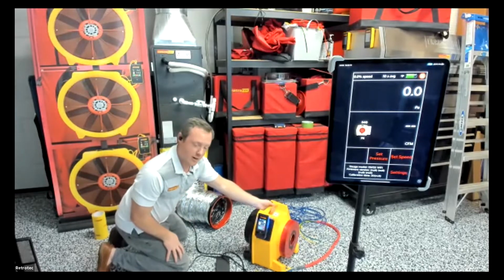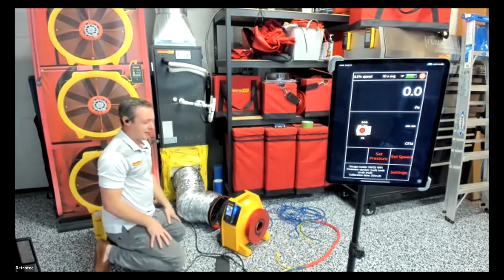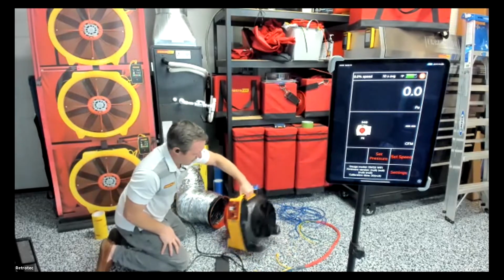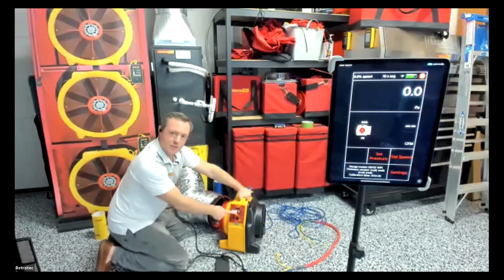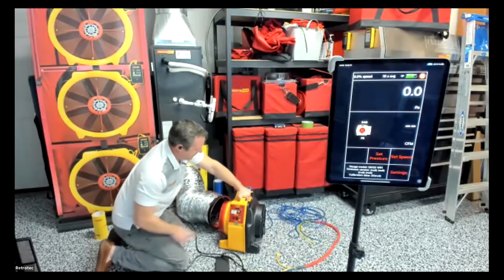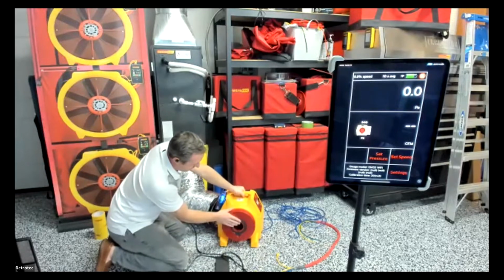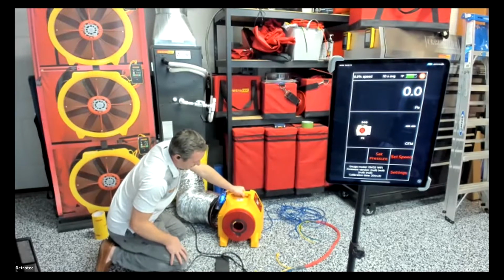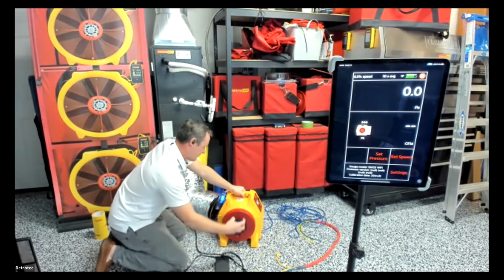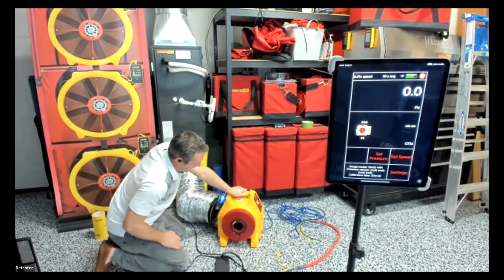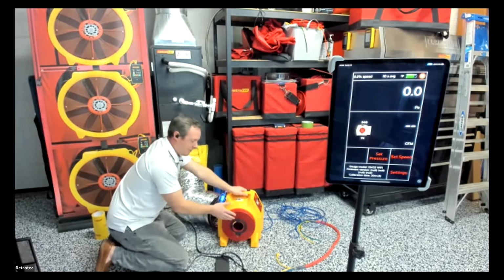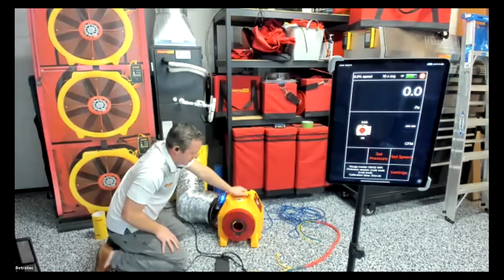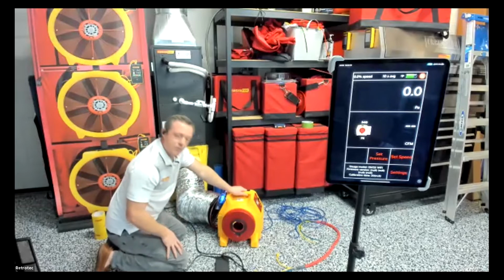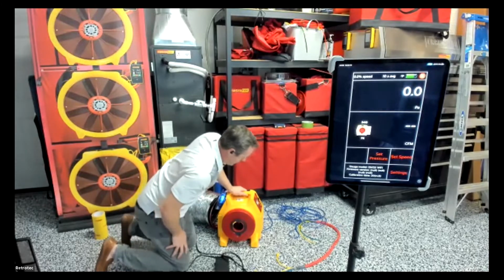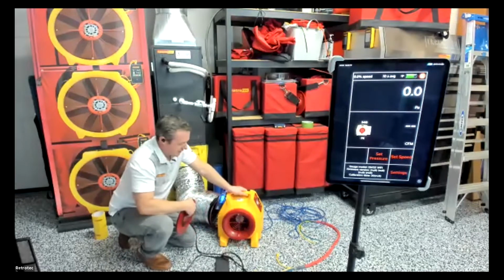You can test in either direction you want. You can do a pressurization test like we're set up here. There's a handy arrow on the other side that shows you which way the airflow is going to go. The side where you adjust the hole size opening is always the inlet side, so air comes in through this way and out the other. The leakier the duct system is, the more open you want this. The gauge tells us if we're in the right range, and we'll get to that in a second. But the way you change these is that's fully open.